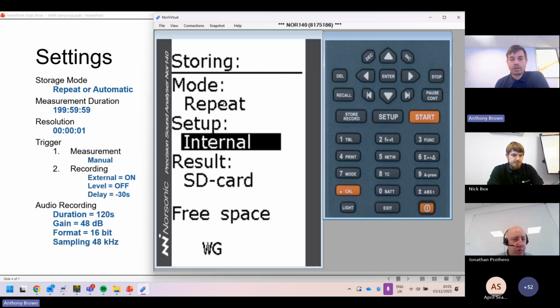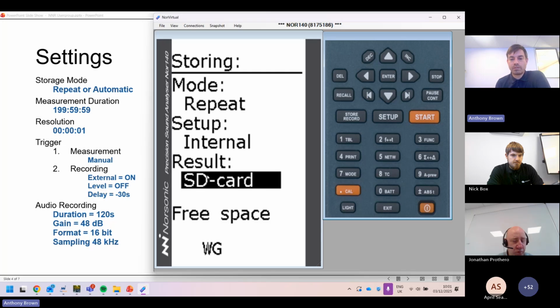The setups we will set to internal. So if you press the arrow down, you can change this from SD card to internal by pressing the inc or dec key, these two here. And then you really want to make sure that this one here, so I press the arrow down, the result is set to the SD card. That makes sure that all the audio files that are captured by the meter are saved to the SD card. Otherwise, you're going to run out of memory on the meter. So repeat, internal, SD card. The top one, mode, can be repeat or automatic. Repeat if you want more than a week. I'm just going to check the chat and just make sure. Yeah, everybody's still keeping up, so we're okay.